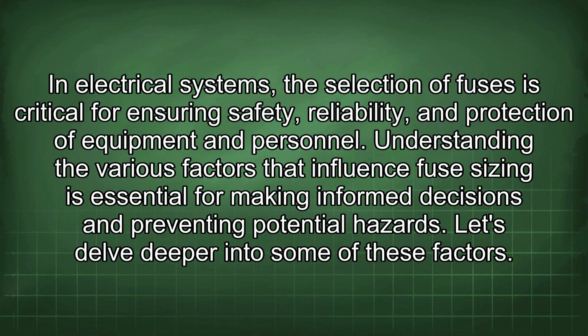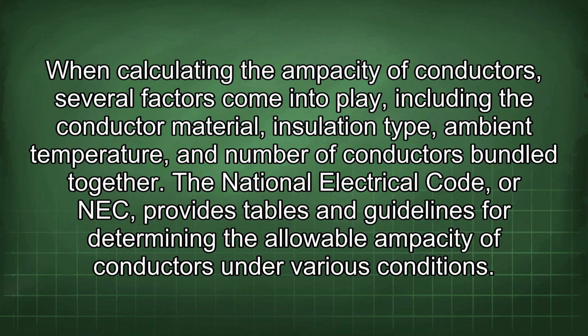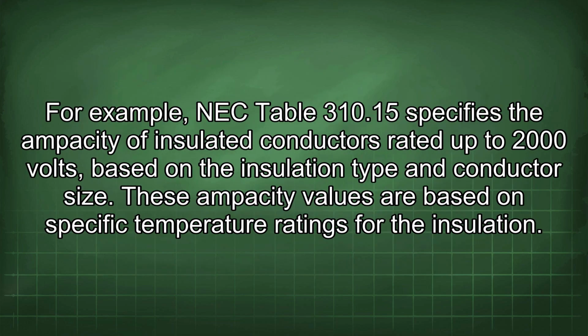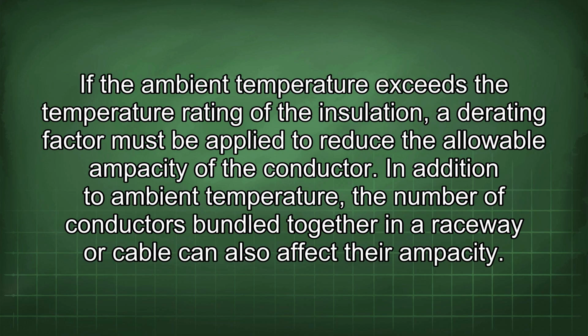Let's delve deeper into some of these factors. When calculating the ampacity of conductors, several factors come into play, including the conductor material, insulation type, ambient temperature, and number of conductors bundled together. The National Electrical Code, or NEC, provides tables and guidelines for determining the allowable ampacity of conductors under various conditions. For example, NEC Table 310.15 specifies the ampacity of insulated conductors rated up to 2000 volts, based on the insulation type and conductor size. These ampacity values are based on specific temperature ratings for the insulation. If the ambient temperature exceeds the temperature rating of the insulation, a derating factor must be applied to reduce the allowable ampacity of the conductor.